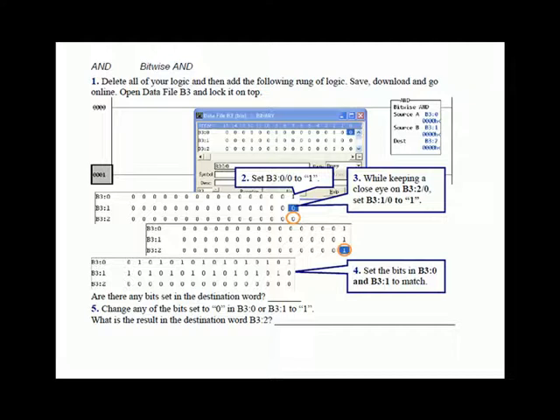Then we had you set the first bit of B3:0 to 1. And then while keeping a close eye on B3:2/0, which is the destination of the bitwise AND instruction, we had you set B3:1 bit 0 to 1. With both of those set to 1, that set B3:2 bit 0 to 1, because this is a bitwise AND.